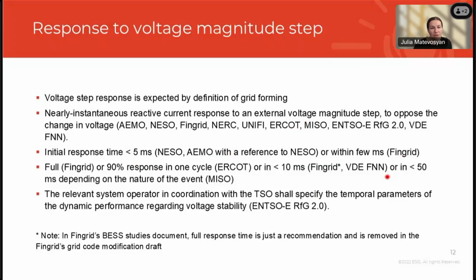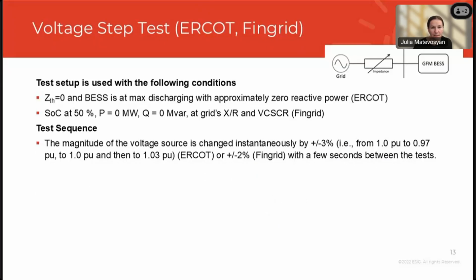One thing I haven't mentioned is that FinGrid, the response times that they currently have in the study specifications for batteries are just recommended values, and it is expected that in the grid code, these values will not be specified. So they basically will require instantaneous or nearly instantaneous response, but will not specify the time for full response. And again, ENTSO-E leaves it to national system operators to define specific parameters of this response.